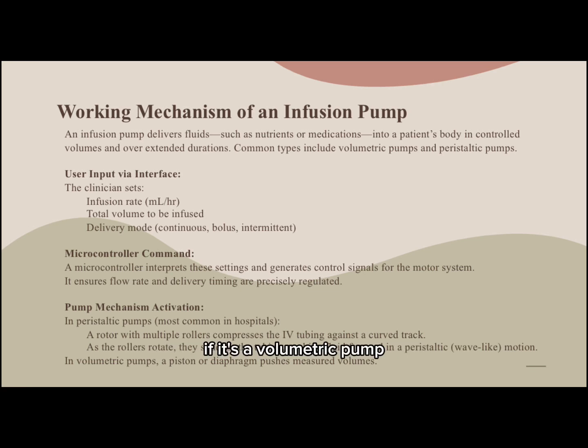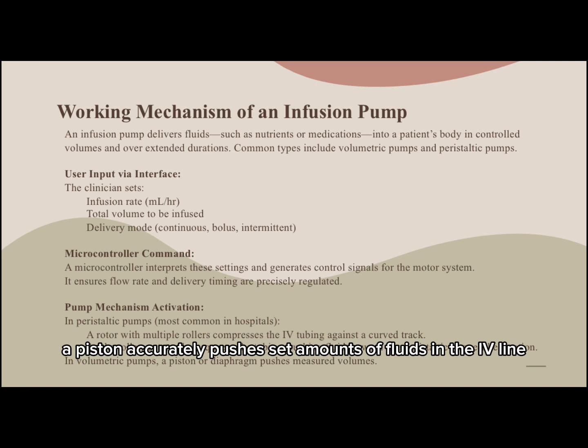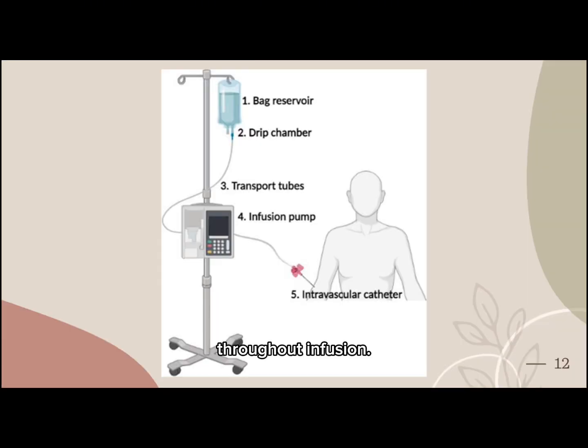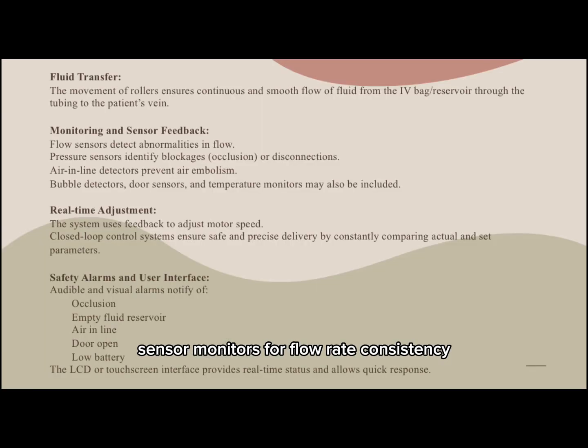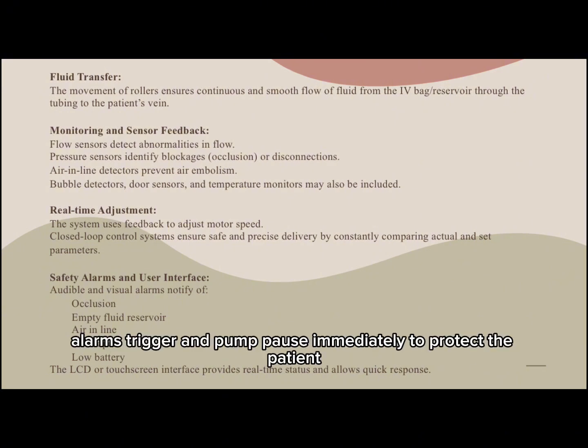If it's a volumetric pump, a piston accurately pushes set amounts of fluid into the IV line. Throughout infusion, sensors monitor for flow rate consistency, pressure changes like blockages or line disconnections, and air bubbles, which can cause fatal air embolisms if unnoticed. If a problem is detected, alarms trigger and the pump halts immediately to protect the patient.